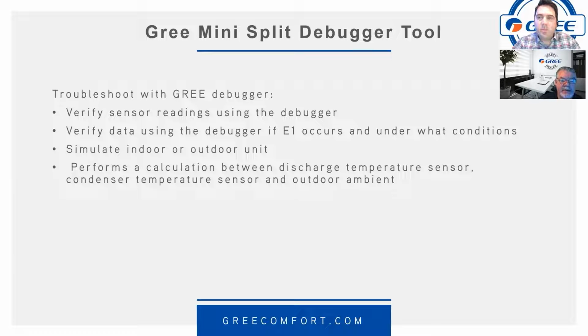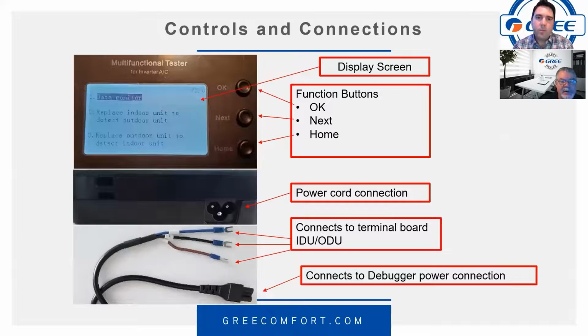So you can verify sensor readings, verify data using the debugger if E1 occurs and under what conditions, simulate the indoor and outdoor unit on the mini splits, and some of the other ones show both values. Perform calculations between the discharge temperature sensor, condenser sensor, and outdoor ambient. It shows you all those values. This is kind of what it looks like: display screen and function buttons, the power cord plugs in, and then these terminals connect to the unit.